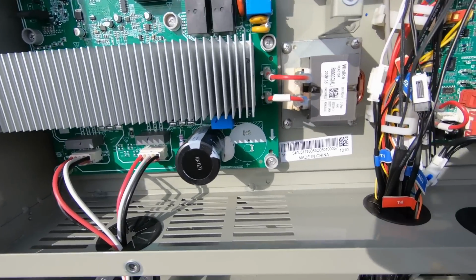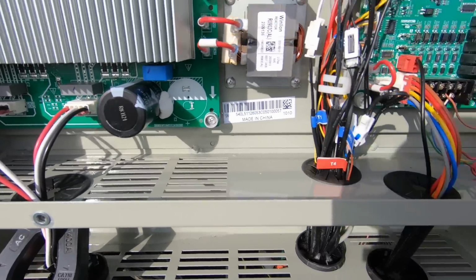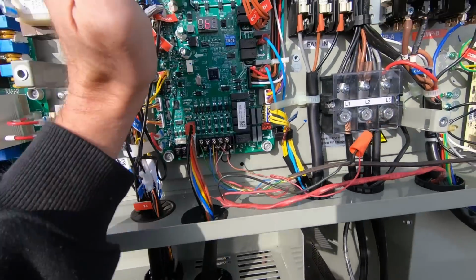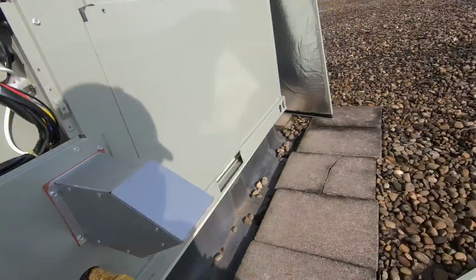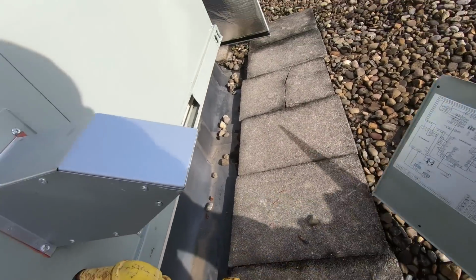Looks like it feeds right here to this board. And the board is showing an E6, which is - I have no memory as I get older - evaporator coil temperature sensor fault for system B.